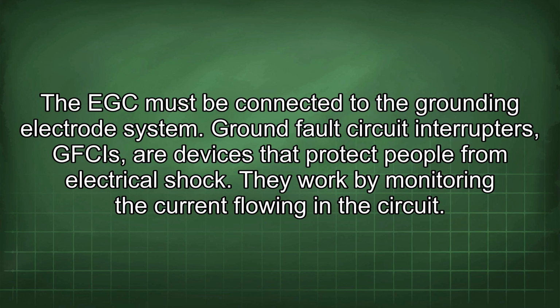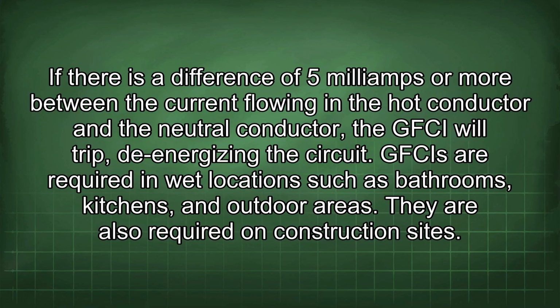Ground fault circuit interrupters, GFCIs, are devices that protect people from electrical shock. They work by monitoring the current flowing in the circuit. If there is a difference of 5 mA or more between the current flowing in the hot conductor and the neutral conductor, the GFCI will trip, de-energizing the circuit.